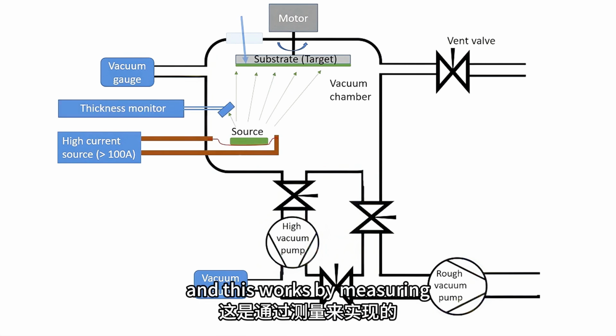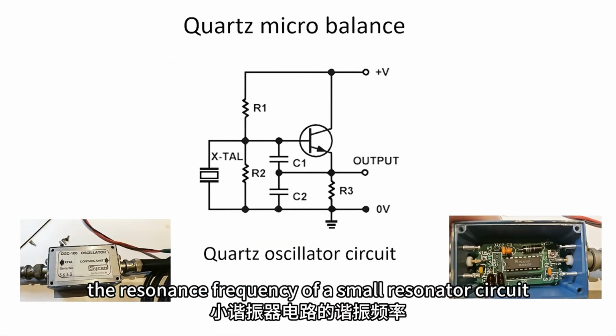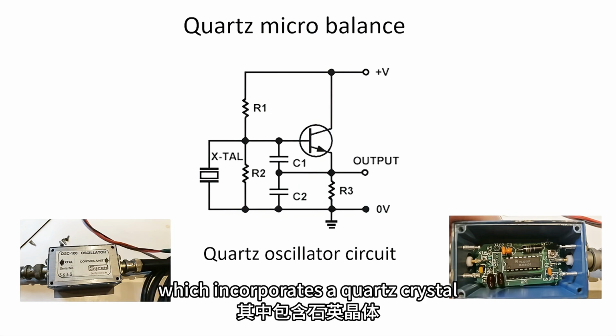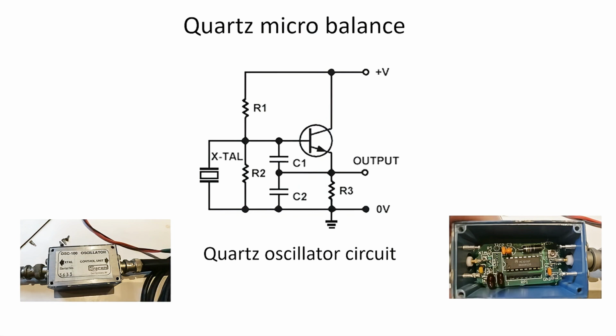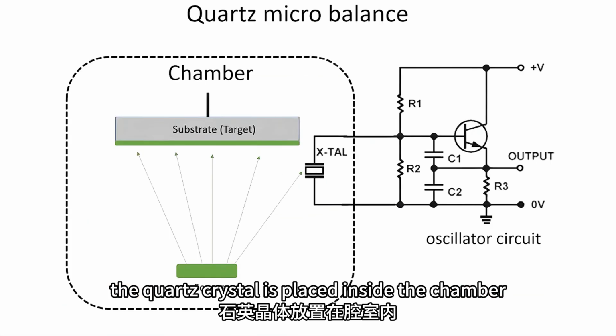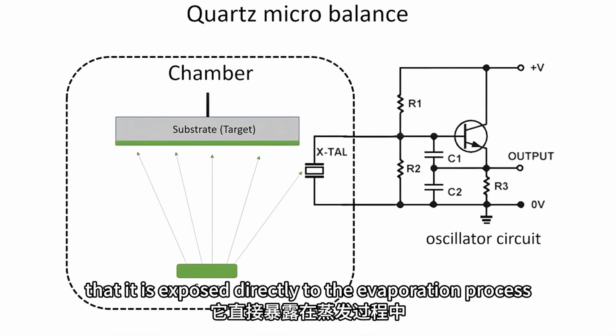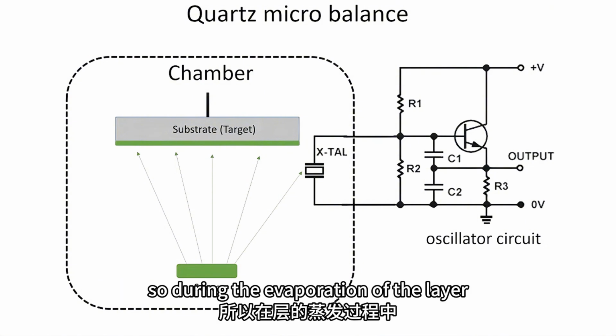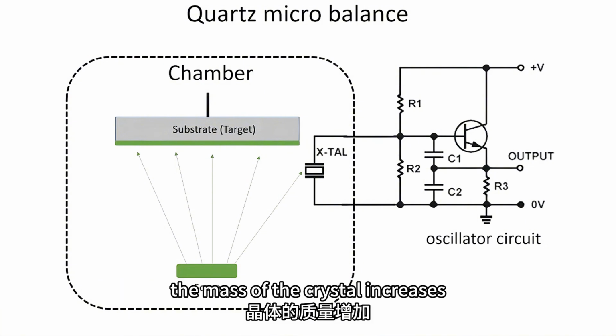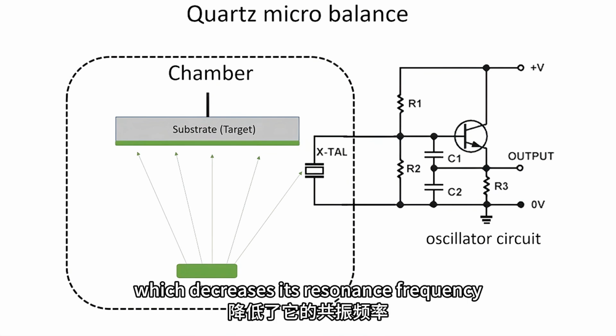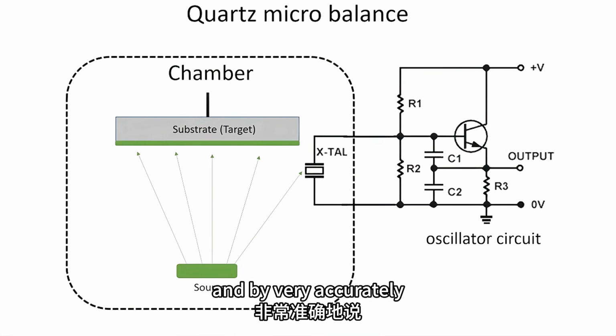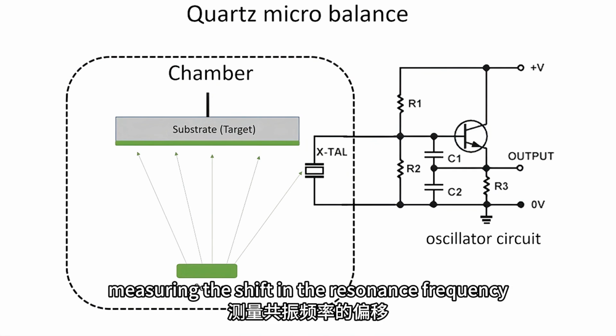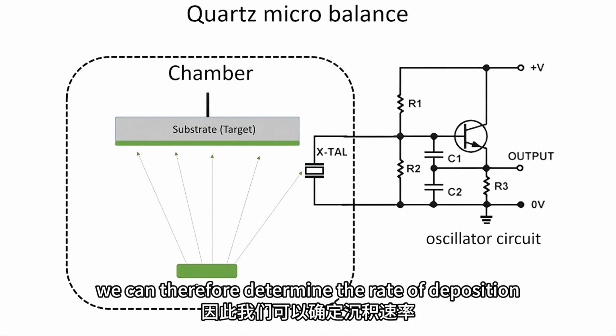And this works by measuring the resonance frequency of a small resonator circuit, which incorporates a quartz crystal. Now, the quartz crystal is placed inside the chamber in such a way that it is exposed directly to the evaporation process. So during the evaporation of the layer, the mass of the crystal increases, which decreases its resonance frequency. And by very accurately measuring the shift in the resonance frequency, we can therefore determine the rate of deposition.